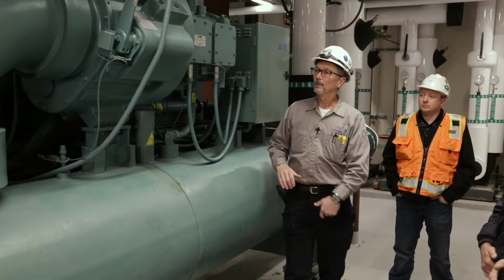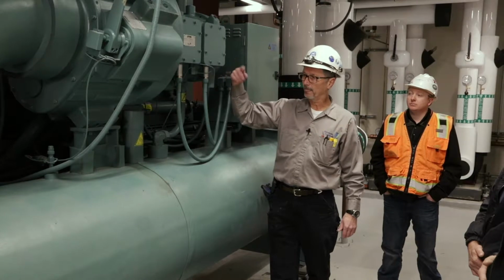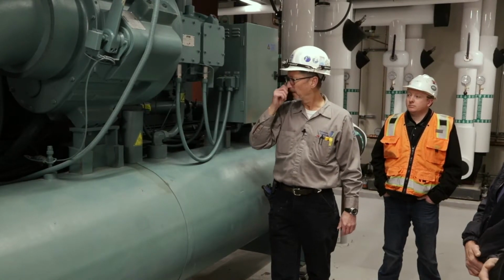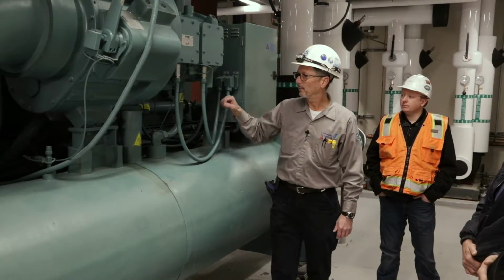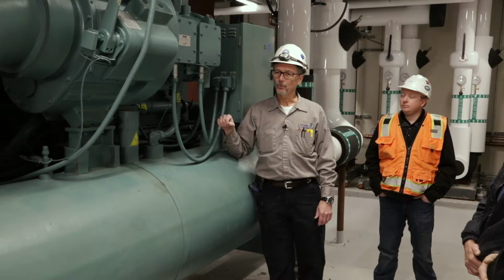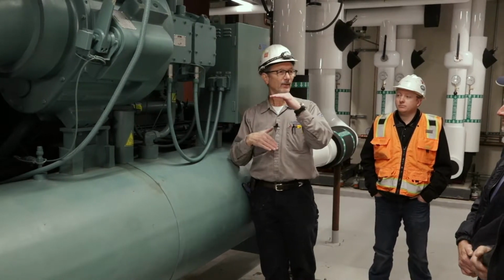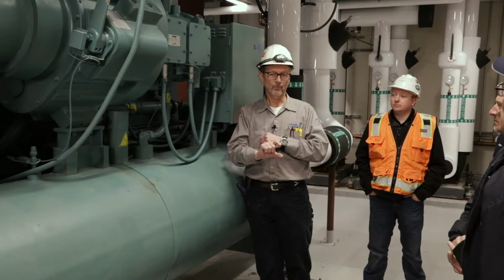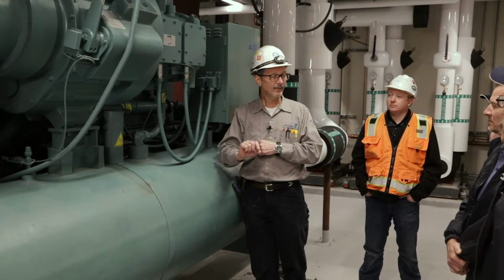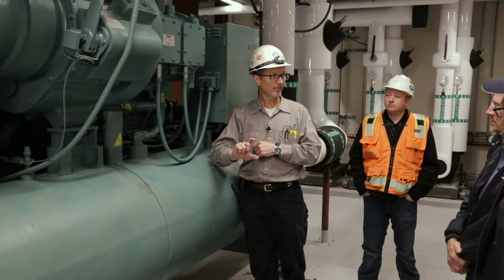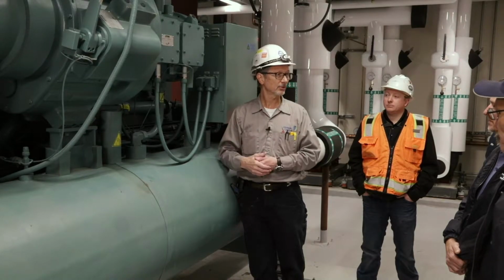And so now the compressor's up and running, and when the refrigerant's going into the condenser, you want to maintain, because of the design of the condenser, it has refrigerant tubes at the bottom that need to have liquid above the top of them to increase the efficiency of the machine.